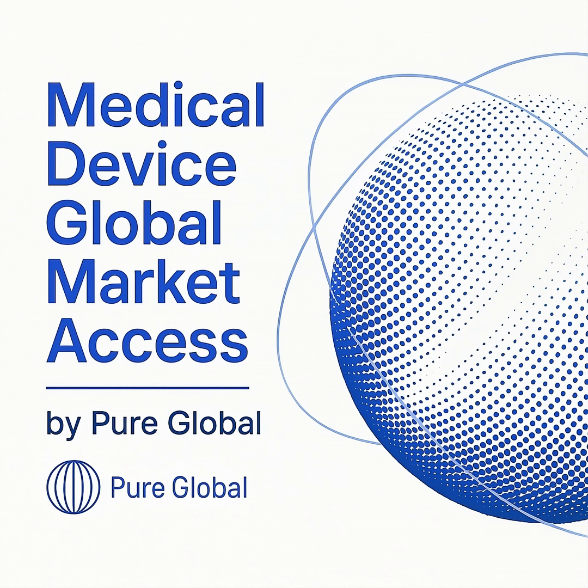Data from design verification and validation, risk management compliant with ISO 14971, biocompatibility testing under the ISO 10993 series, and software validation can often be repurposed for your 510K submission. This is because both the EU and the FDA recognize many of the same international standards.